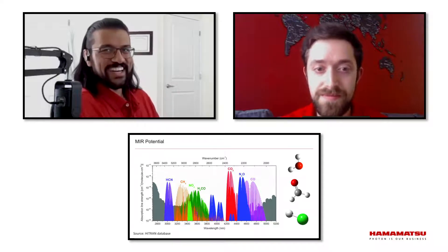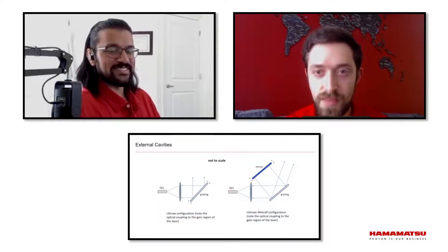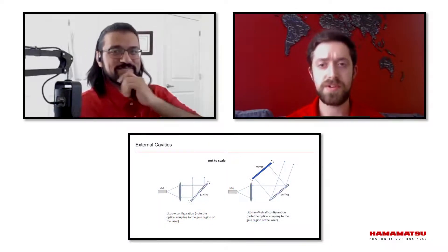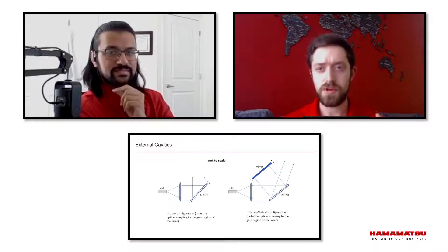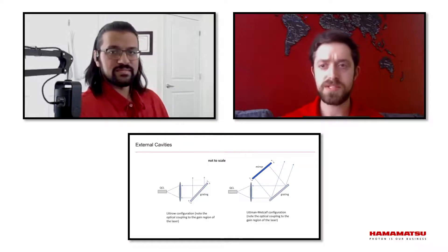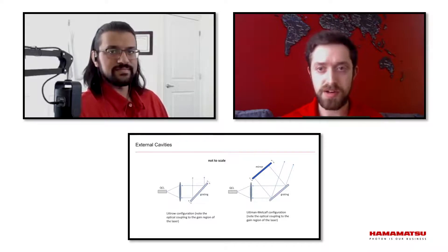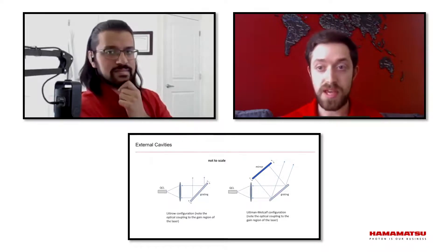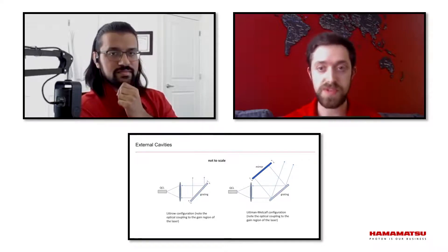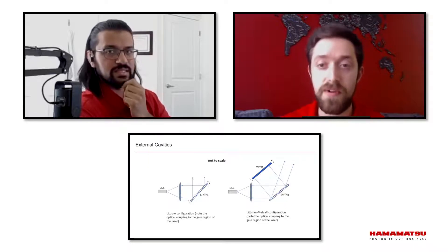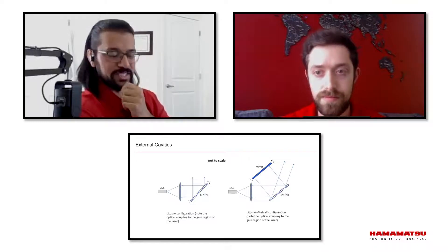Wait a second — FTIR? How could a QCL fit into a broadband high-specificity application like that? It's important to note that there are different types of quantum cascade lasers. One is an external cavity laser. To put it simply, you start with a base chip, and then there is a very sophisticated optical system around the broadband gain chips that achieves certain wavelengths and allows you to tune or scan through them. With this system, you will be achieving a broad output that is necessary for FTIR. So that scanning function even allows broadband QCL options.